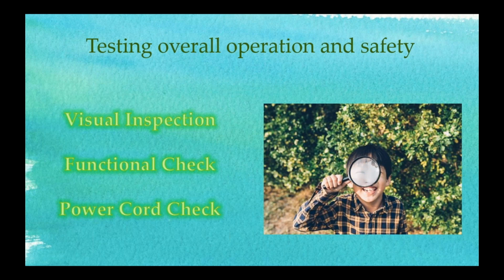you're going to think, oh, that's nothing, we do that all day. The power cord on a portable x-ray machine, I usually replace every 2 years whether it needs it or not. Think about it: it's on a coiled recoil spring, and that goes in and out time and time again every day, right? They let it go from about 5 feet and it recoils, boom, hits it. The 3 prongs on your plug hit the ground. Those bend, all kinds of problems. So it's something simple, a basic power cord, but it's important to check it on routine maintenance for sure.